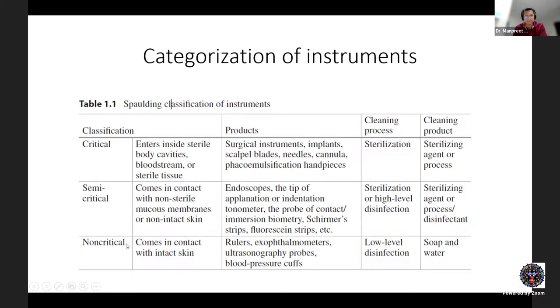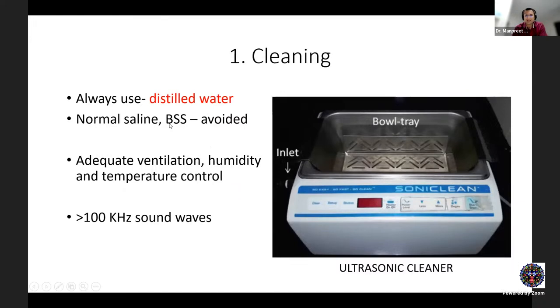Remember the Spaulding classification for your examinations — Earl Spaulding from Philadelphia. Once a surgical procedure is over, the first thing to do is cleaning. Always use distilled water — do not use normal saline or BSS, as they contain ions, calcium, and other minerals. Adequate ventilation, humidity, and temperature control of the cleaning room is also very important.